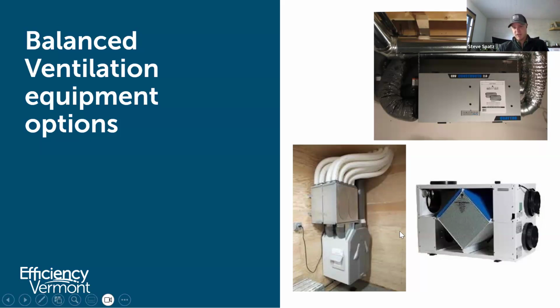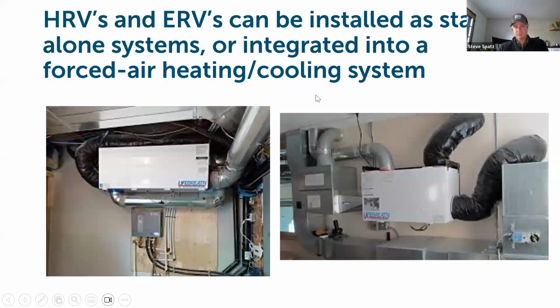So you have a lot of flexibility in that unit to be able to dial in your flows room by room. But if you are doing a site-built rigid pipe duct system connected to the ERV or HRV, you really should be designing into that dampers and terminals that you can use to adjust flows, because you want to be able to dial this piece of equipment and the system in once it is installed. The code does allow for the integration of HRVs or ERVs into a forced air heating system and shared ductwork.